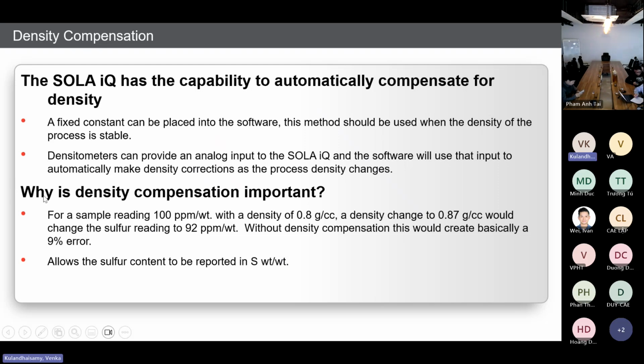So why is density compensation important? It is very important. Say a sample reading is 100 ppm per weight with a density of 0.8 gram per cc. A density change to 0.87 gram per cc would change the sulfur reading to 92 ppm per weight. Without density compensation, this would create basically a 9% error. In order to overcome the 9% error, density compensation is very important. So if the customer's process density varies from time to time, then they should use the live density compensation method.